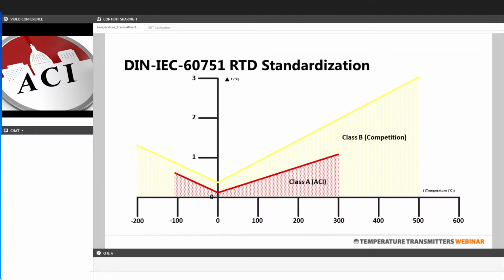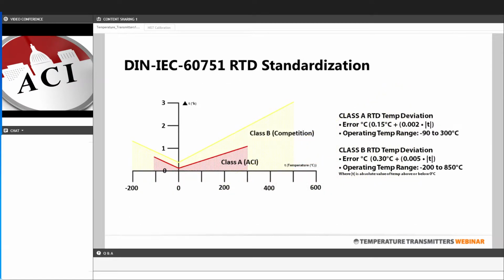These devices all use, for standard temperature ranges, Class A RTDs, and that's unique to ACI. We only use Class B RTDs in our high temp and low temp transmitters, whereas most of our competitors use Class B RTDs across all of their temperature transmitters. The Class A RTDs simply provide a higher level of accuracy and repeatability compared to Class B, but they have a narrower operating range. So we use those for all of the standard ones, but the high and low temps, we use our Class B RTDs.